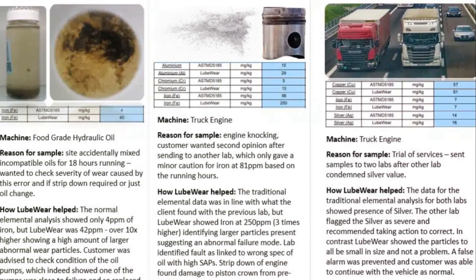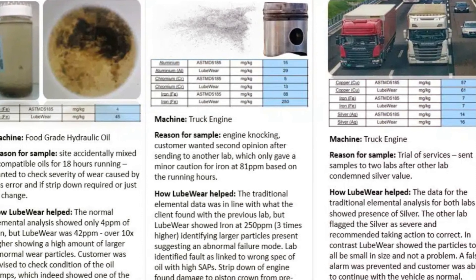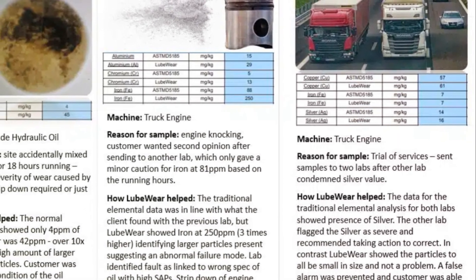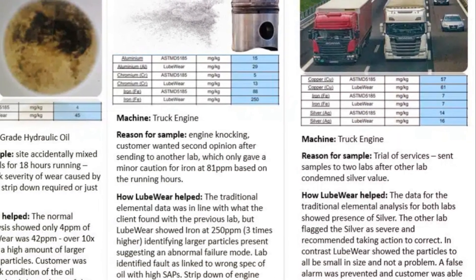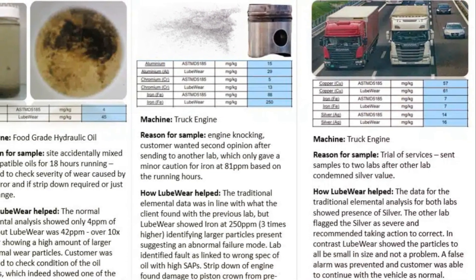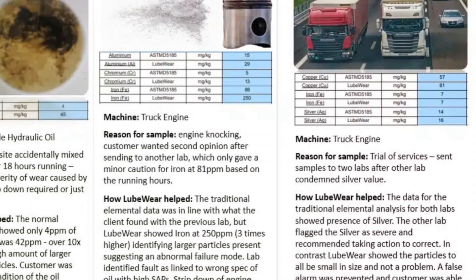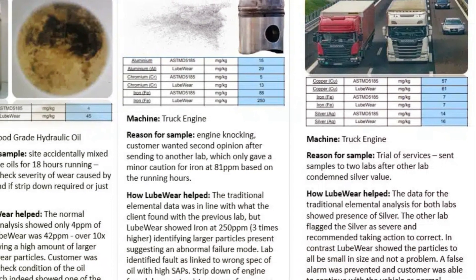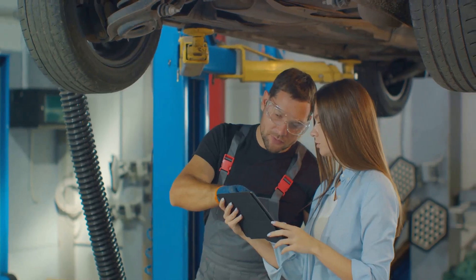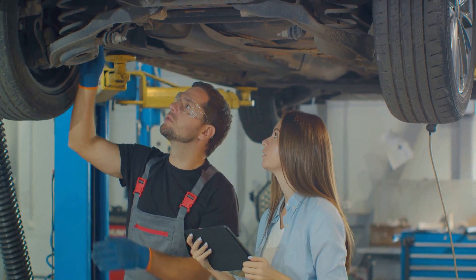Take LubeWear rapid acid digestion for instance. This technique helps us detect wear and tear at an early stage, before other CBM techniques including traditional wear metal analysis, all by simply comparing the wear concentration with and without acid digestion. This gives us how much abnormal wear is present, enabling us to intervene before significant damage occurs. If you pause the video, you can look at a couple of case studies, or visit LearnOilAnalysis.com to see more case studies of LubeWear and how this can help your machinery.